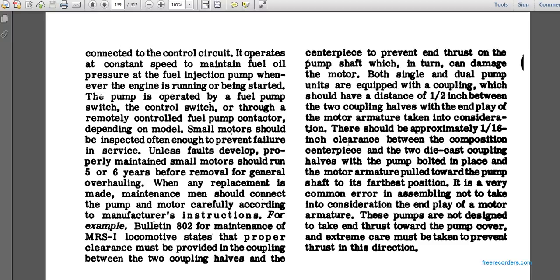The small motor should be inspected often enough to prevent failure in service. A properly maintained small motor can run five to six more years before removal or overhaul. Maintenance men should connect the pump motor carefully according to the manufacturer's instructions. For example, bulletin 802 for the MRS1 locomotive states the proper clearance of the coupling between the two coupling halves and the centerpiece prevents thrust on the pump shaft. There should be approximately one-half inch between the two coupling halves and one-sixteenth inch clearance between the composition centerpiece and the two die-cast coupling halves, with the motor armature pulled toward the pump shaft in its farthest position.